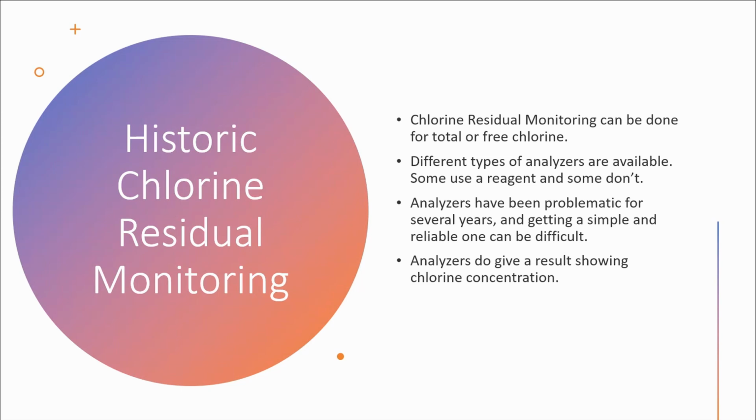Yeah, very much so. The key there, I think, really is, make them put their money where their mouth is. Make them demo the analyzer. Whether they're willing to demo it tells you whether they're going to stand behind that product. Yeah, pilot it for a couple weeks. Yeah, that's all it takes, really. Most of the stuff that we've tried, within the first week, we have a pretty good idea how much work it's going to take to keep that analyzer within calibration specs and how much O&M is required with it.